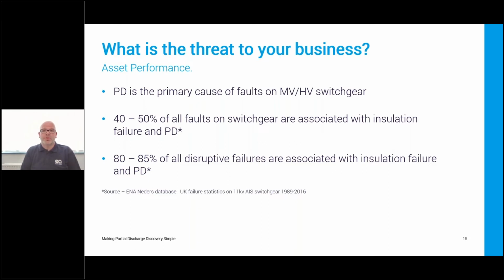So we know that PD is the primary cause of faults on medium voltage and high voltage switchgear. How do we know that? Well, according to the Energy Network Association's Neders database, which I'm sure many of you are familiar with, around half of all faults on 11 kV switchgear are associated with PD-related insulation failure. And worse than that, 80% or 8 out of 10 of all disruptive failures, so that's failures that resulted in outages, are associated with PD-related insulation failure. So hopefully that gives you some idea of how important this topic really is.